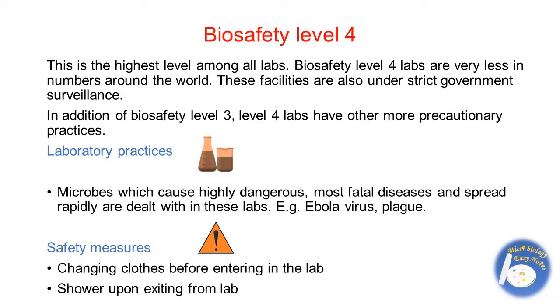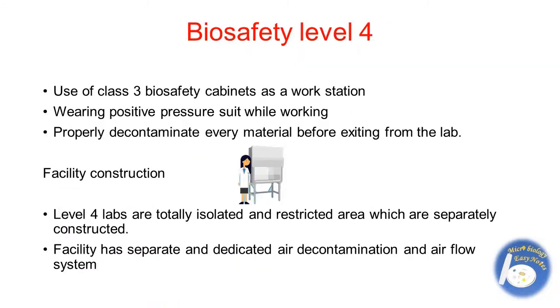Safety measures include changing clothes before entering the lab, showering upon exiting the lab, use of Class 3 biosafety cabinets as a workstation, and wearing a positive pressure suit while working. Every material must be properly decontaminated before exiting the lab. Level 4 labs are totally isolated and restricted areas which are separately constructed, with a separate and dedicated air decontamination and airflow system.